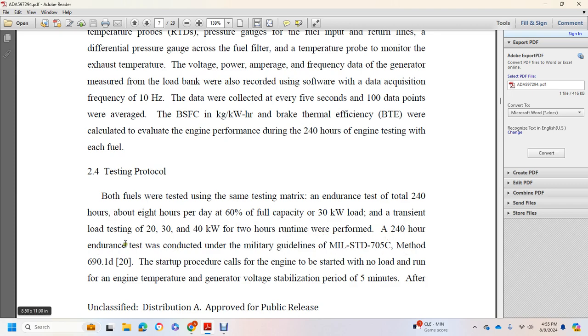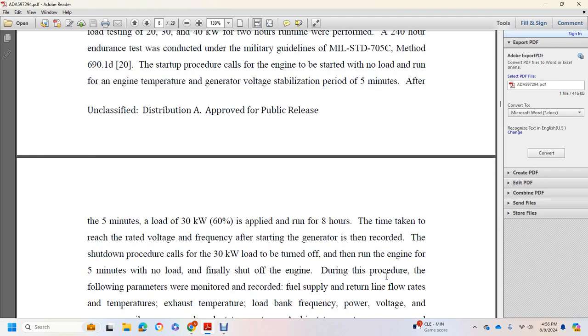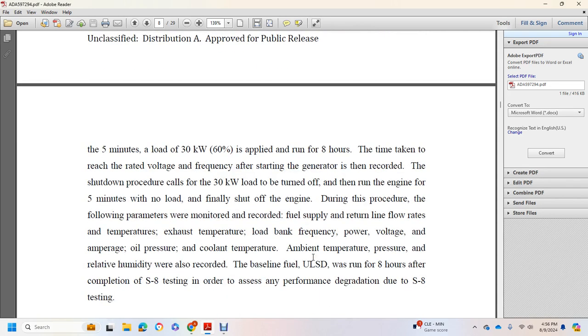A 240-hour endurance test was conducted under the military guidelines, Military Standard 705C, Method 690.1d. Startup procedures call for the engine to be started with a no-load run for a stabilization period of 5 minutes. After the 5 minutes, the load of 30 kilowatts at 60% is applied with a run for 8 hours. The time taken to reach the rated voltage and frequency after starting the generator is recorded. Shutdown procedures call for the 30 kilowatt load to be turned off and the engine run for 5 minutes with no load. Then the final shutdown of the engine.